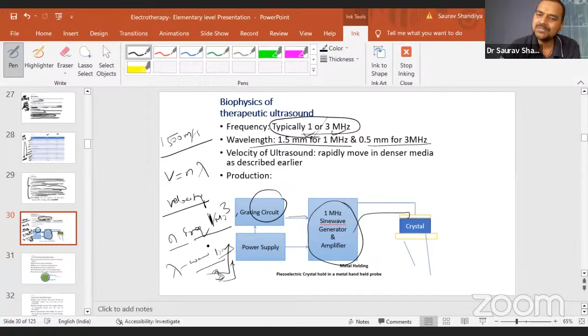Now what happens, and frequency will be 1 per second kind of thing, because we have selected 1. So now if you take a 3 megahertz machine, the frequency you have increased to 3, the wavelength will automatically be divided by 3. Why? Now if you are increasing n three times, then lambda you have to divide by 3, so that it cancels out and gives you again the value of n lambda, which is exactly V. So the real velocity will remain the same always. To keep the velocity the same, you have to select the frequency of the machine. According to that, the wavelength will change. Okay, so this is not a big problem.